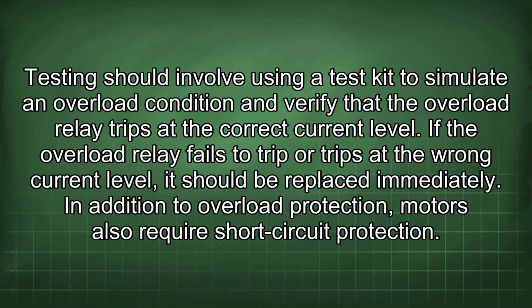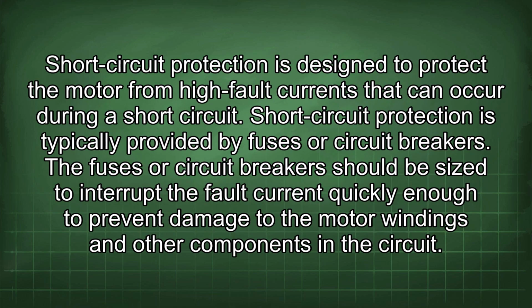If the overload relay fails to trip or trips at the wrong current level, it should be replaced immediately. In addition to overload protection, motors also require short-circuit protection. Short-circuit protection is designed to protect the motor from high fault currents that can occur during a short circuit. Short-circuit protection is typically provided by fuses or circuit breakers. The fuses or circuit breakers should be sized to interrupt the fault current quickly enough to prevent damage to the motor windings and other components in the circuit.